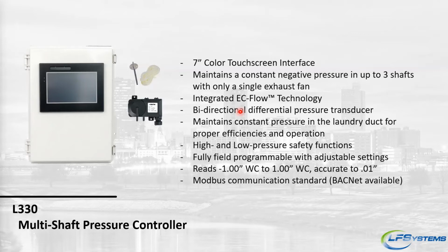And the only issue that caused for us is, well, how do we control that in a variable speed system? So we introduced the L330. What we do now is we take the L150 and replace it with this L330, and we put 3 sensors, 1 in each shaft. Basically, we can look at the highest, the lowest, or the average of the 3 sensors and modulate the fan accordingly. So now, instead of having 3 small fans, we now have 1 larger fan.